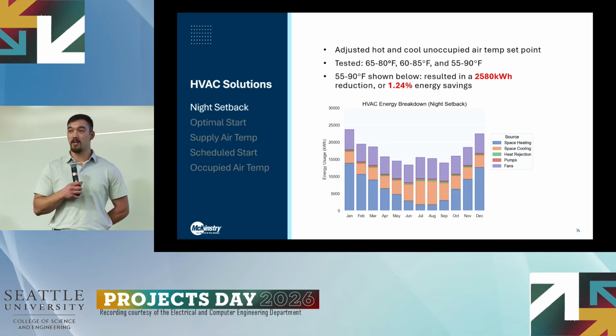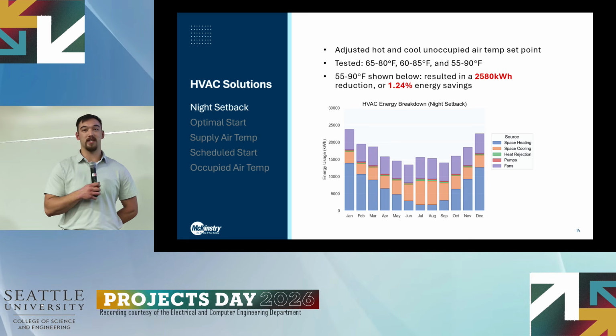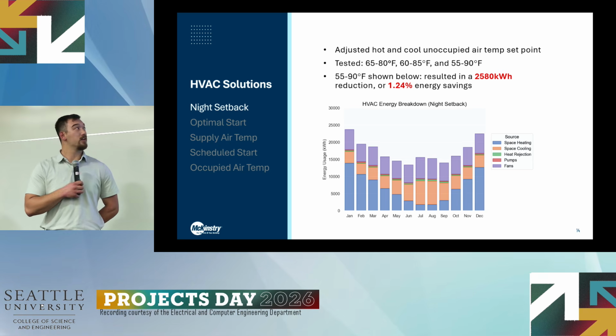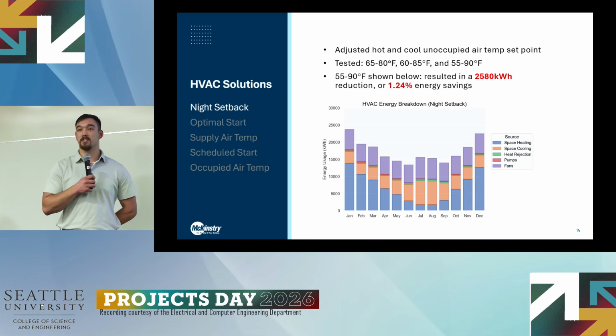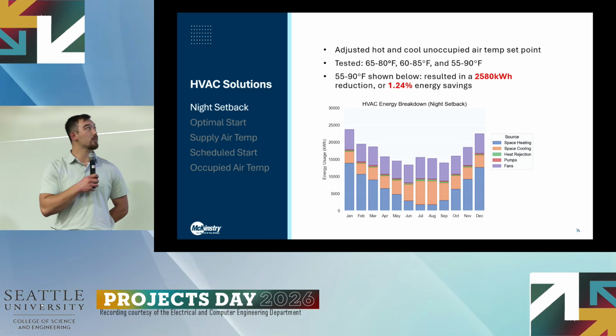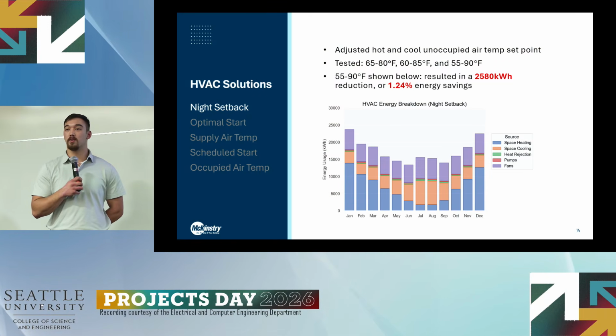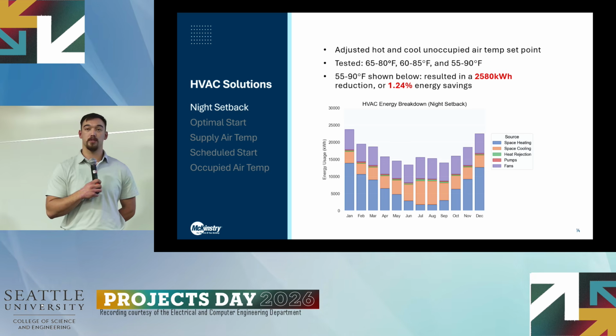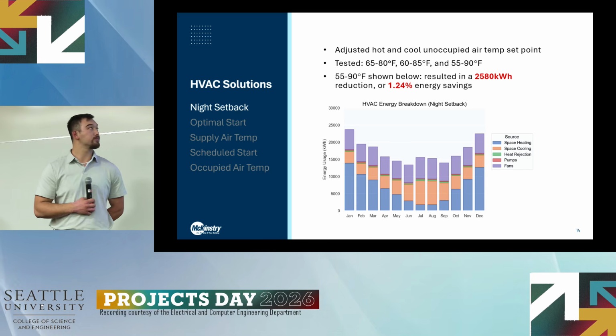We tested the wider bands, and this resulted in a reduction of energy usage. We followed this until we saw a point of diminishing returns, and that was at 55 degrees, where the heating would turn on, and at 90 degrees, where the cooling would turn on. And that resulted in a 2,600 kilowatt hour reduction, or about 1.2% energy savings.